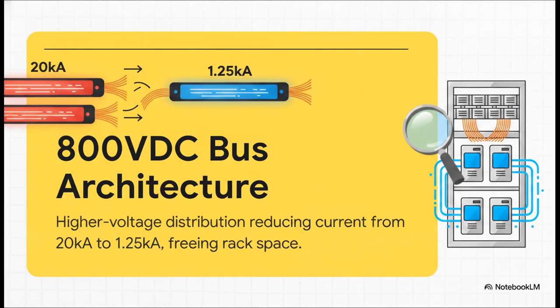This brilliantly illustrates how engineers solved that exact crisis: by switching to an 800-volt direct current bus architecture, they reduced the current requirement from 20,000 amps down to a highly manageable 1,250 amps. This massive boost in efficiency shrinks the amount of copper needed and frees up crucial physical space in the server rack for, you guessed it, more processing power.